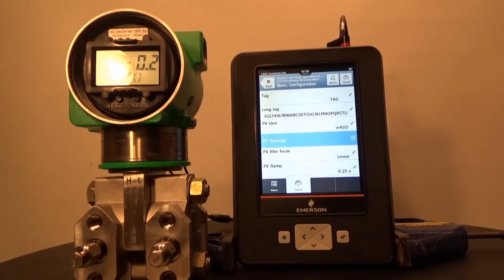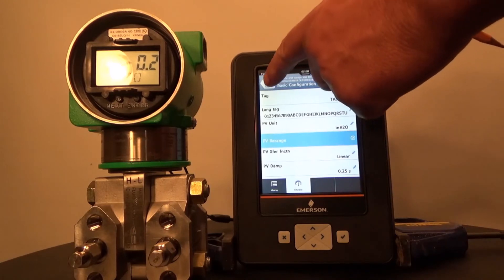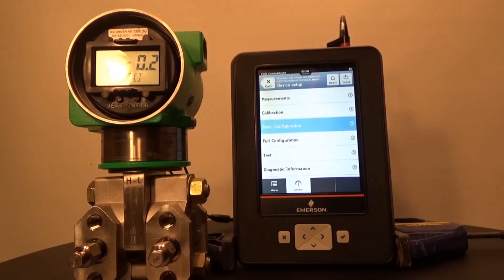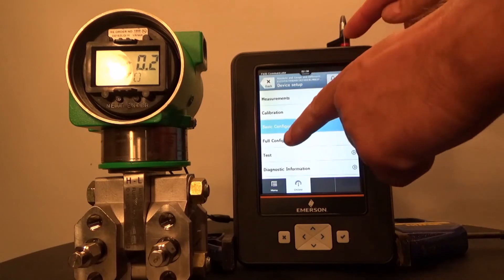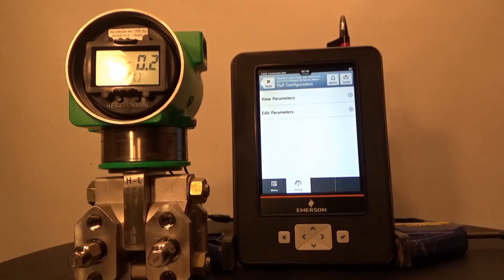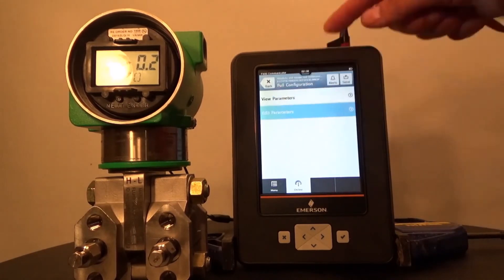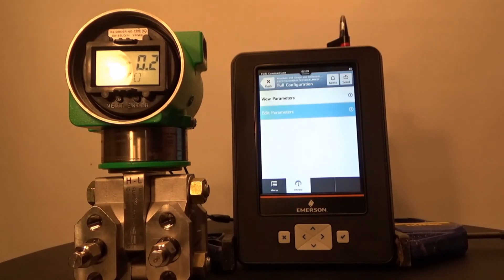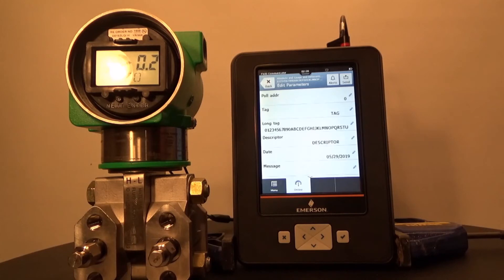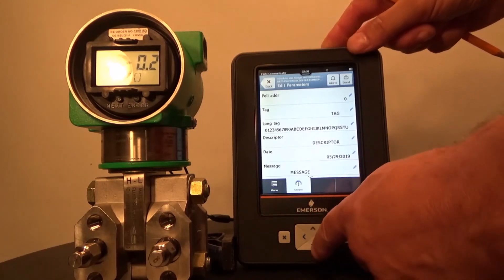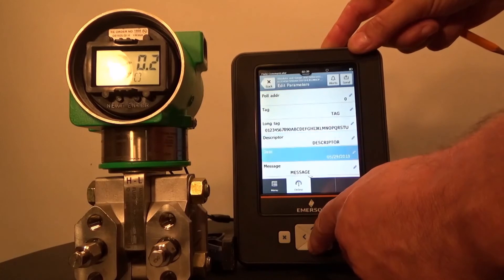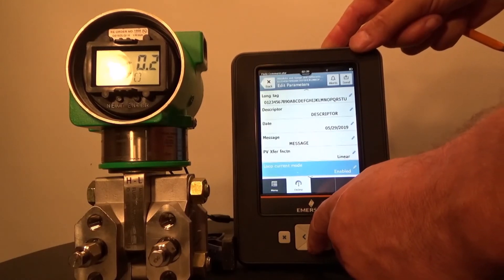It will return to the Basic Configuration menu. From the Basic Configuration menu, select the back button again and you will be sent to the Device Setup menu. From the Device Setup menu, select Full Configuration. From the Full Configuration menu, select Edit Parameters. From the Edit Parameters menu, we want to select PV Unit, so we will need to scroll down until we see that on the display.